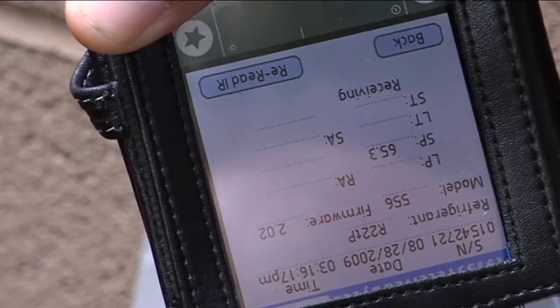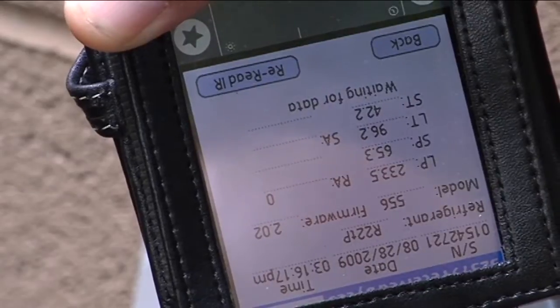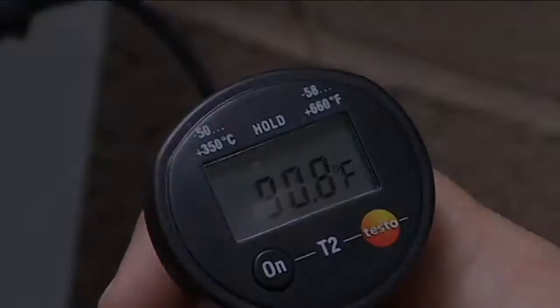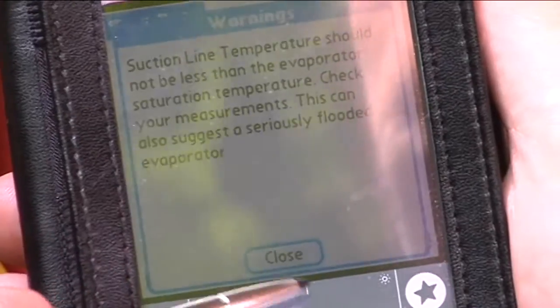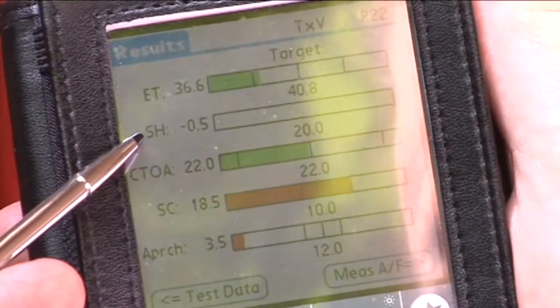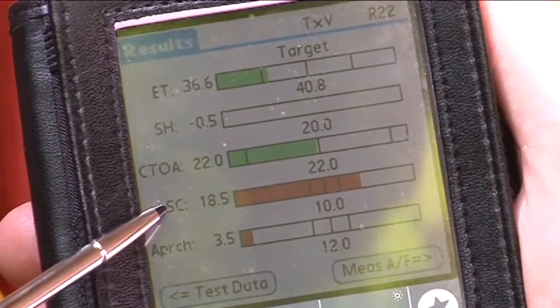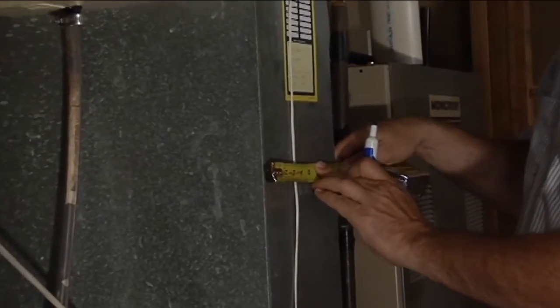Now no technician can manipulate this data. After we get the data into the palm, we're going to go ahead and get the outdoor air temperature and put that into the palm. We'll hit next to see our preliminary results. There's a warning screen, and we're going to continue. The reason there's a warning is because our superheat is down at minus 0.5, which means we essentially have none. Everything else looks normal except for the subcooling, which appears to be high. So we're going to check the airflow to see if it is a charge or an airflow problem.